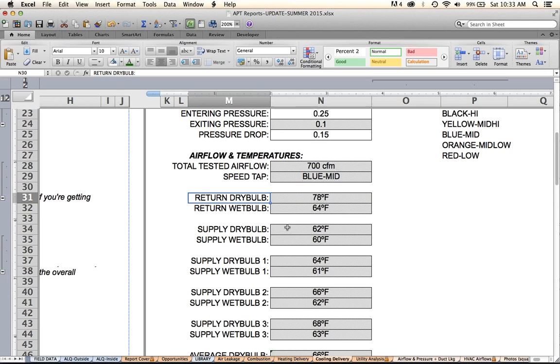Okay, so the next thing we're going to do is take the return and the supply dry bulb and wet bulb. And that's important only in cooling mode. When we go into heating delivery over here, which I have not done yet, I'm just finishing up with the cooling side, you're only going to have to do dry bulb. That means just a thermometer, like a cooking thermometer would be fine. In this case, because we're trying to measure cooling and drying with air conditioning, you have to have a thermometer that does both of these things. They're a little bit more expensive for sure. So we've got a return dry bulb of 78 and a wet bulb of 64 and a supply dry bulb of 62 and a wet bulb of 60.